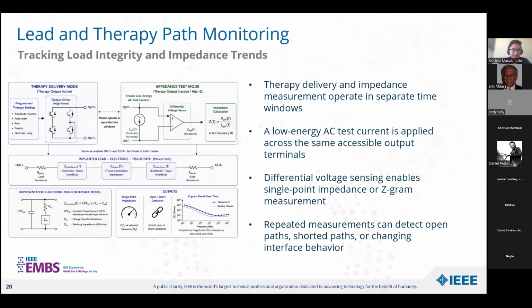path leakages we have. So the model I'm showing at the bottom is like an illustration of that electrode tissue interface. It's just an example. So it shows us how complex and frequency dependent it can be. So a high impedance measurement in this monitoring can suggest that we might have an open or a disconnect path, while a low impedance can suggest a short or an insulation issue, right?